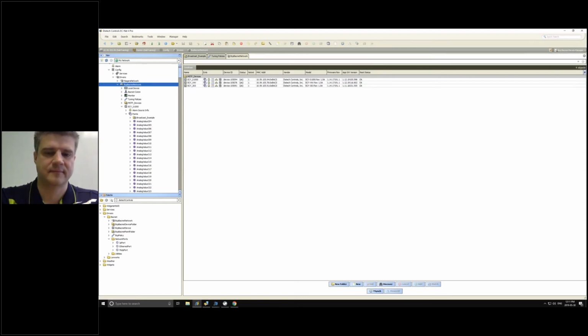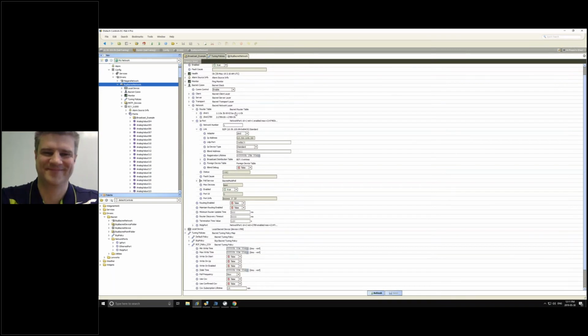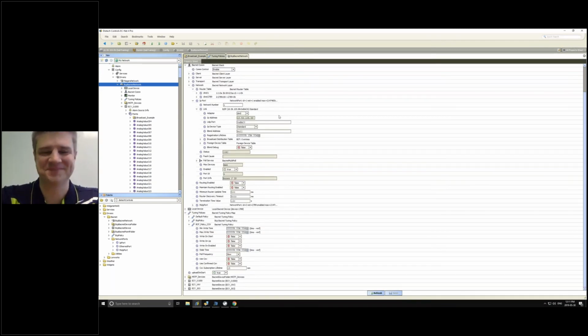It's not that we advise you to expose controllers to the internet, but if we had 2 controllers on the internet, we could actually route to them on entirely different addresses in entirely different places on the planet. As long as we had a network path to them, and of course we were talking on port 47808, which is what we're doing for BACnet, we could poll those devices and get data. So no, they don't need to be on the same subnet.